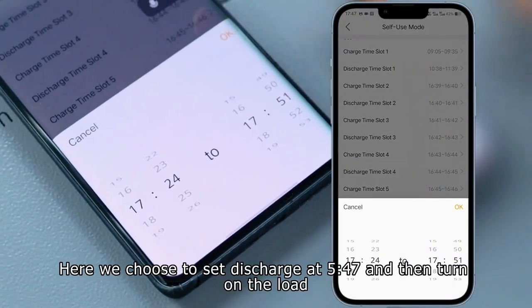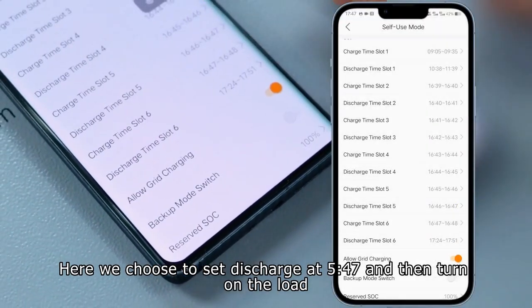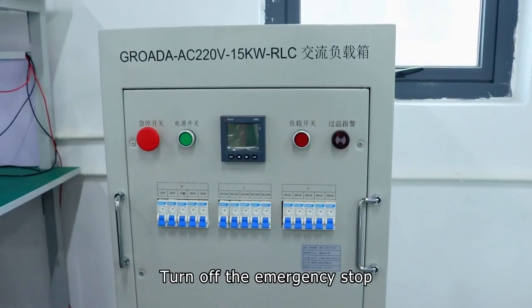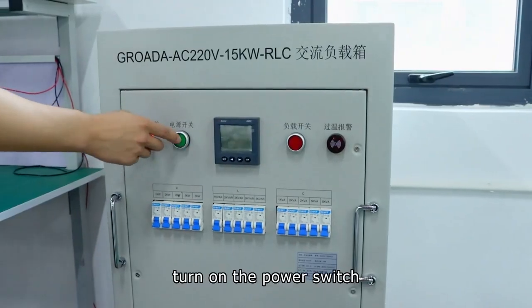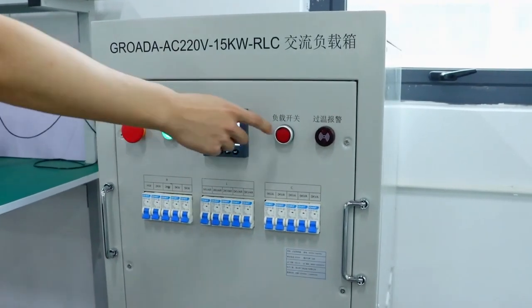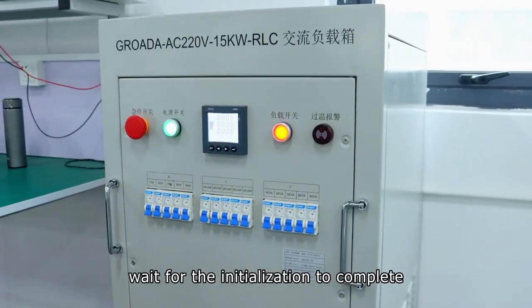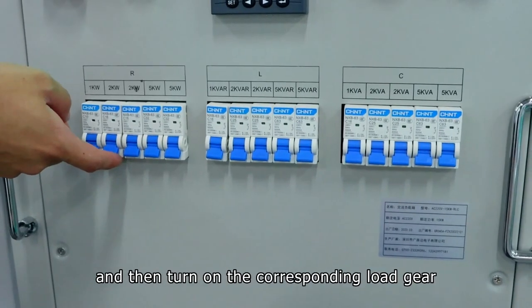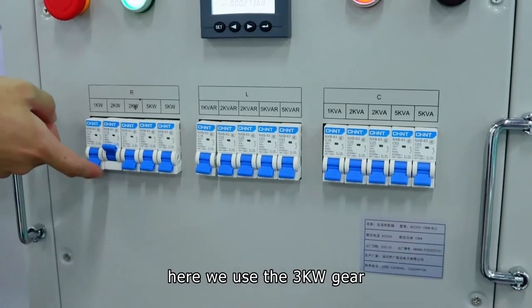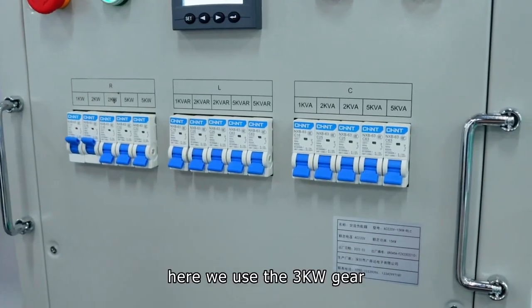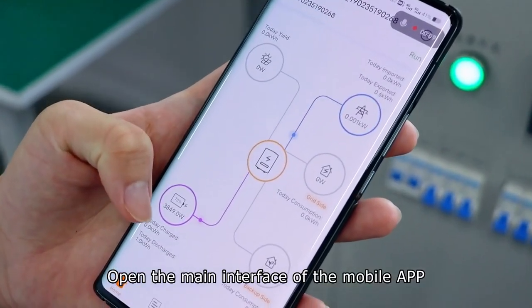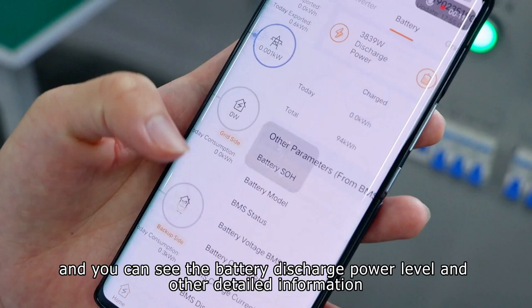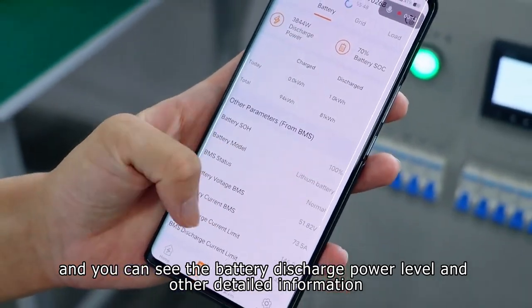Here we choose to set discharge at 5:47, and then turn on the load. Turn off the emergency stop. Turn on the power switch. Turn on the load switch, wait for the initialization to complete, and then turn on the corresponding load gear. Here we use the 3 kW gear. Open the main interface of the mobile app, and you can see the battery discharge power level and other detailed information.